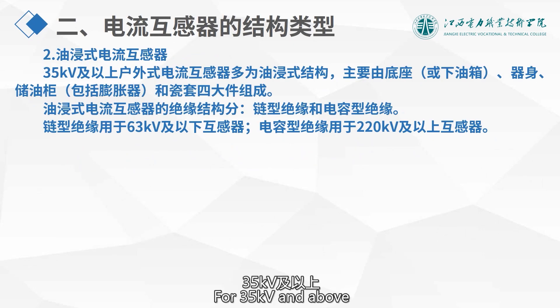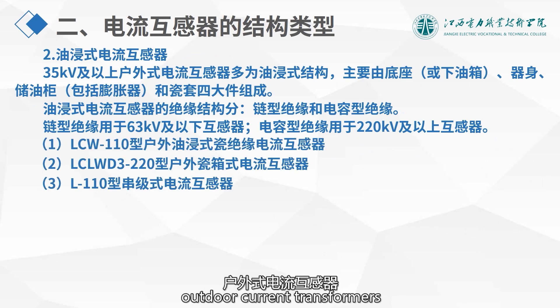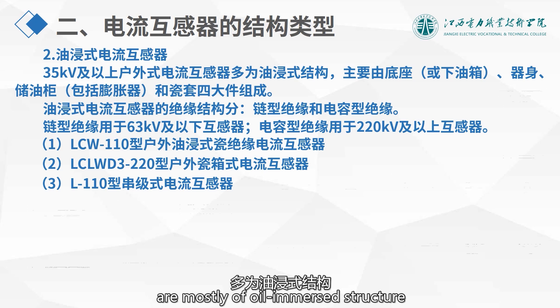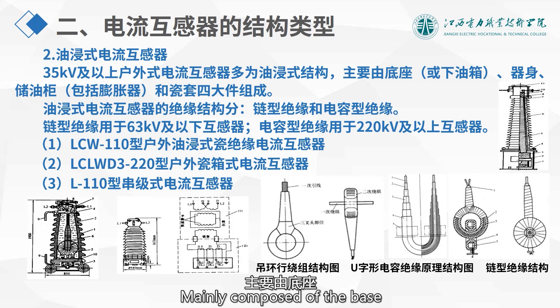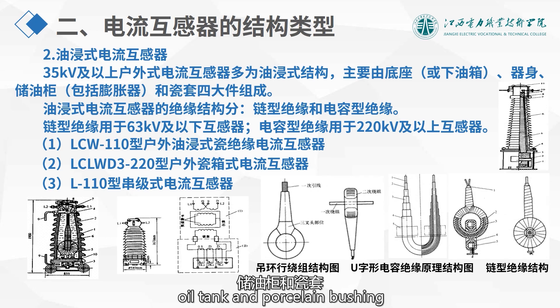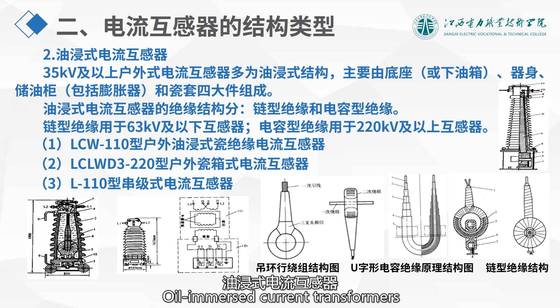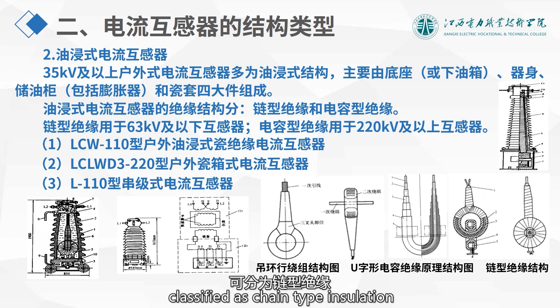For 35 kV and above, outdoor current transformers are mostly of oil-immersed structure, mainly composed of the base body, oil tank, and porcelain bushing as the four main components. Oil-immersed current transformers have two types of insulation structures: chain type insulation and capacitive type insulation.